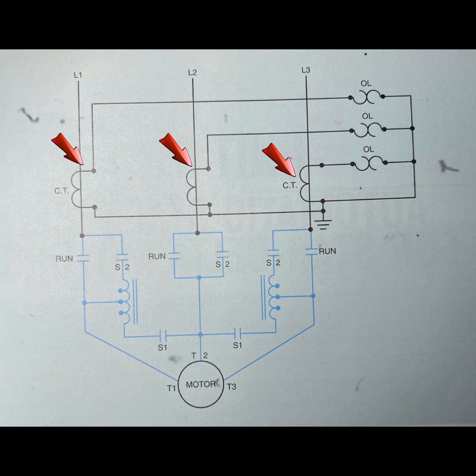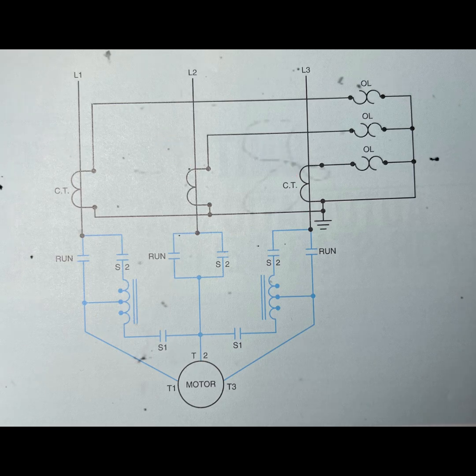The CT designations in the above image indicate current transformers. These transformers are used on large motor starters to step down the current so that a conventional overload relay and heater size may be used. Magnetic overload relays are used on large, reduced voltage starters also.